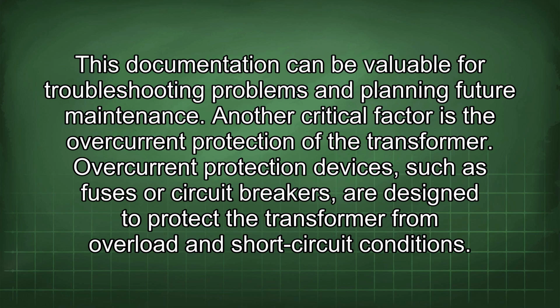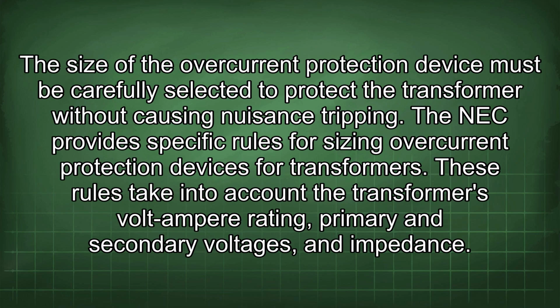Another critical factor is the overcurrent protection of the transformer. Overcurrent protection devices, such as fuses or circuit breakers, are designed to protect the transformer from overload and short-circuit conditions. The size of the overcurrent protection device must be carefully selected to protect the transformer without causing nuisance tripping. The NEC provides specific rules for sizing overcurrent protection devices for transformers. These rules take into account the transformer's volt-ampere rating, primary and secondary voltages, and impedance.